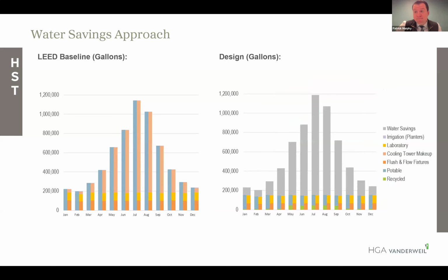And in our proposed design we ended up pulling all the heating and cooling equipment into the building. We eliminated the cooling tower altogether. It was such a dramatic impact on maintenance and also on water consumption. We just did without it. So we used what's called an air-cooled chiller instead. We were just rejecting that heat to the atmosphere with no water evaporation. It's a little bit less efficient from a cooling perspective, but it has its benefits, certainly on the water side. So you're seeing we just chopped the top of that water mountain off. And that allowed us to have some pretty dramatic savings.